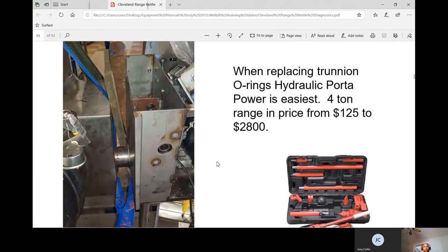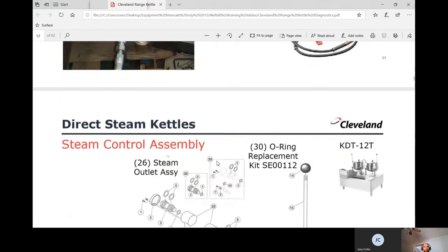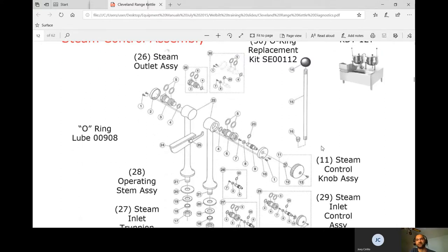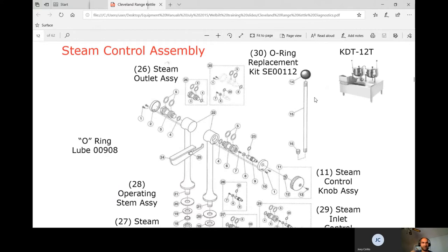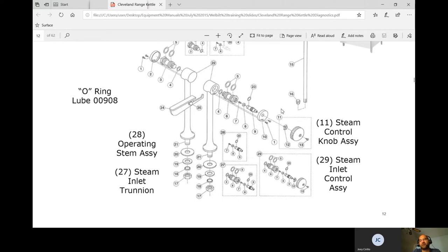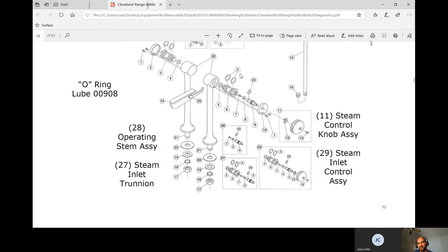They're showing here how to replace a trunnion O-ring using Porta Power. Here's the assembly of the red handle inlet valve — these are common for leaking from the O-rings. You must use the specific O-ring lubricant from Cleveland; otherwise the O-rings will dry out. Leaks typically occur if the unit is over-steaming or if water enters — caused by a scaled boiler or a malfunctioning water level probe filling too high. Water damages these O-rings, and the complaint you'll get is hot steam or water dripping out when it's on. These are pretty simple to replace.